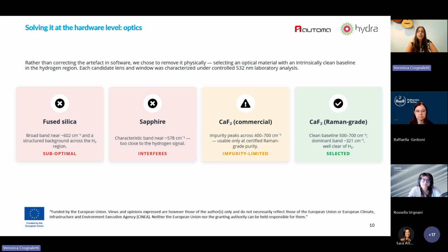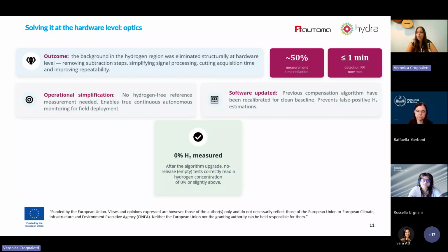For this reason, we have tried to correct this artifact, not only in a software way, but also in a physical hardware way. We selected different types of optical materials, both lenses and windows, and chose the best one: calcium fluoride Raman grade optics, lenses and windows, thanks to its clean baseline in the hydrogen region. So the background in the hydrogen region was eliminated at the hardware level with this optics.